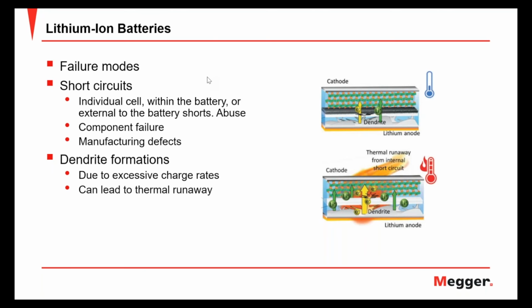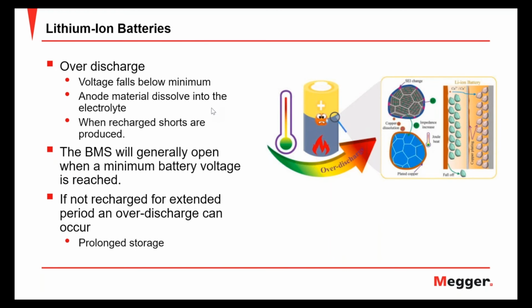And as I mentioned before, as you get excessive charge rates, you can get lithium plating that can pierce a separator and lead to a thermal runaway situation. Over discharging also can cause problems. When voltages fall below a minimum, anode material dissolves into the electrolyte, and this can also lead to dendrite formation that can pierce separators. Now, the BMS will generally open the battery when a minimum battery voltage is reached in order to protect everything.